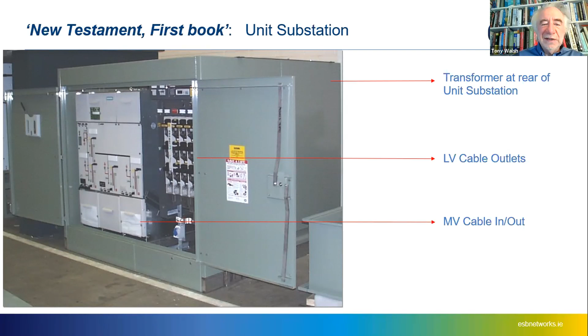If we took the roof off the substation, we'd see the transformer. We've got the MV in red, the LV in black. It's a 630 kVA transformer. If we want to put in more capacity, and this is an existing substation, then we've no room. The transformer would be too big. So we need a transformer that will have a greater power density. And what we found was that to get the greater power density and be able to cut off some of the fins so that we could make it larger and yet not overheat the substation, we used a lower loss transformer. So we used copper in the transformer because it has lower losses.